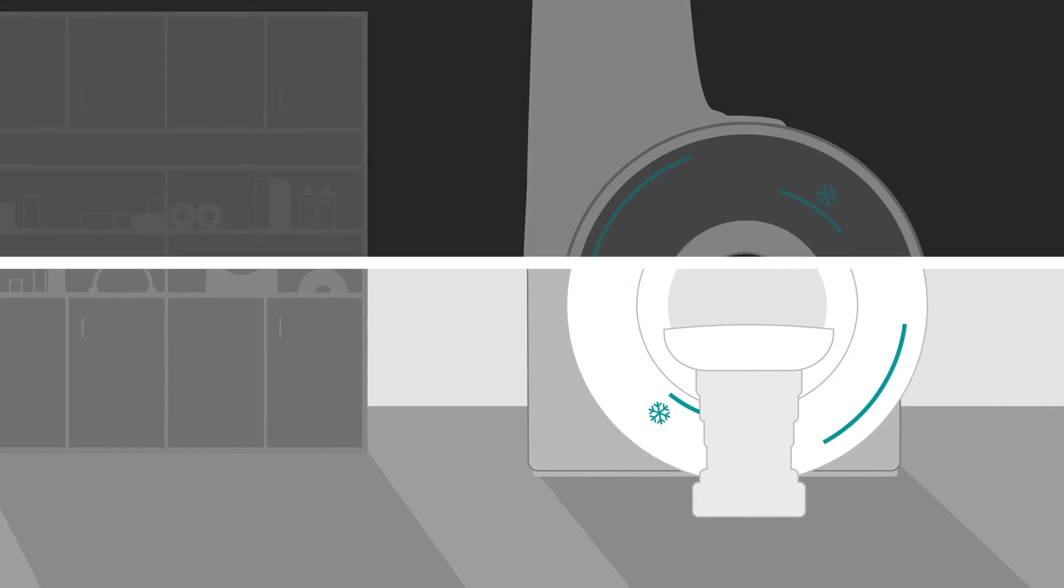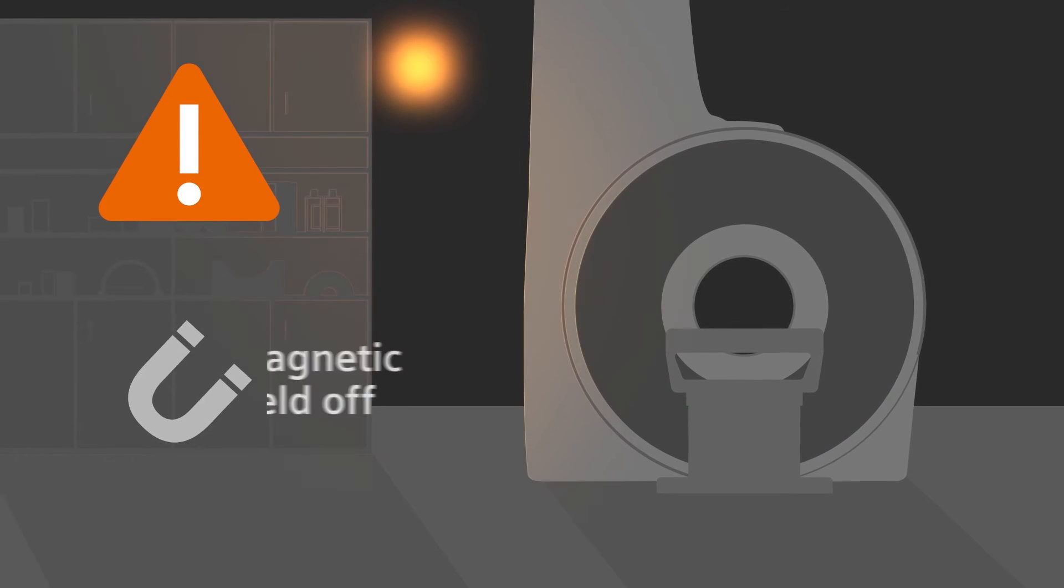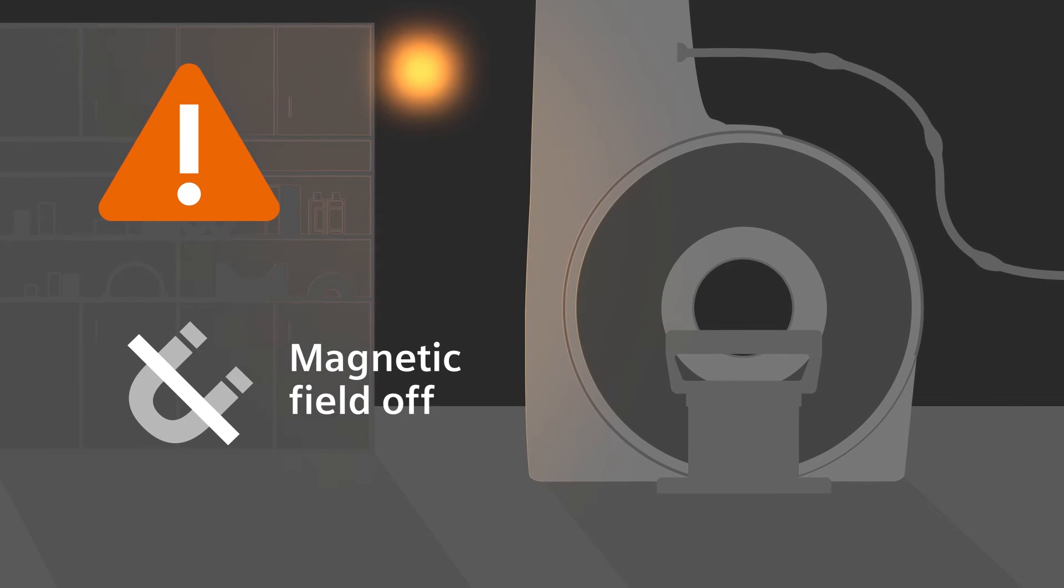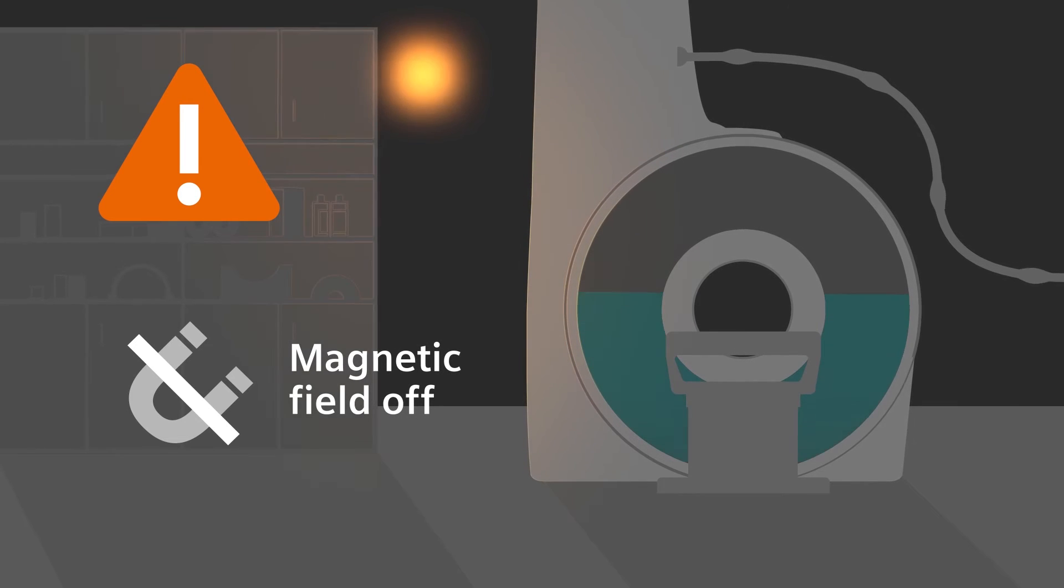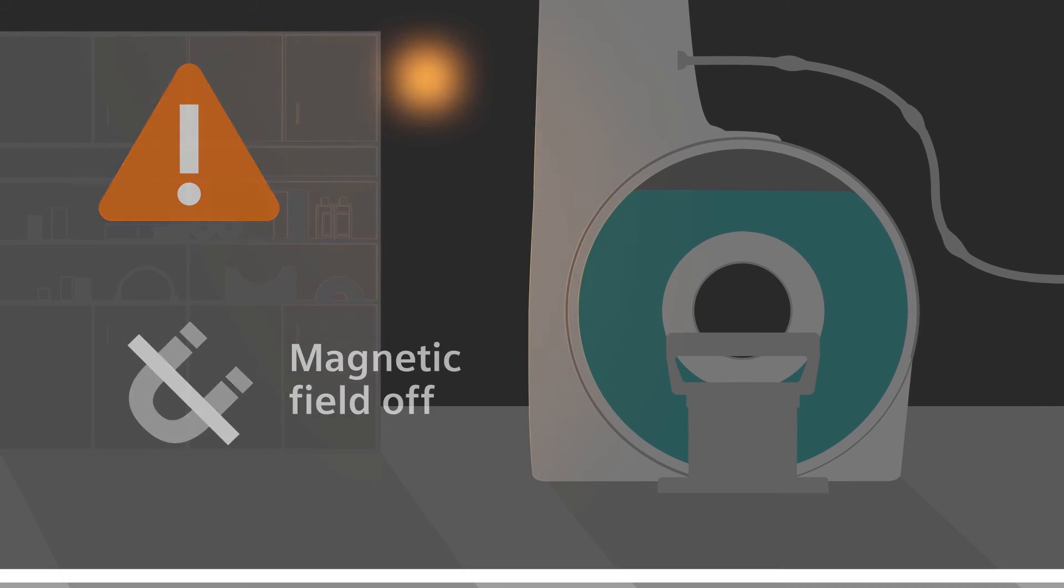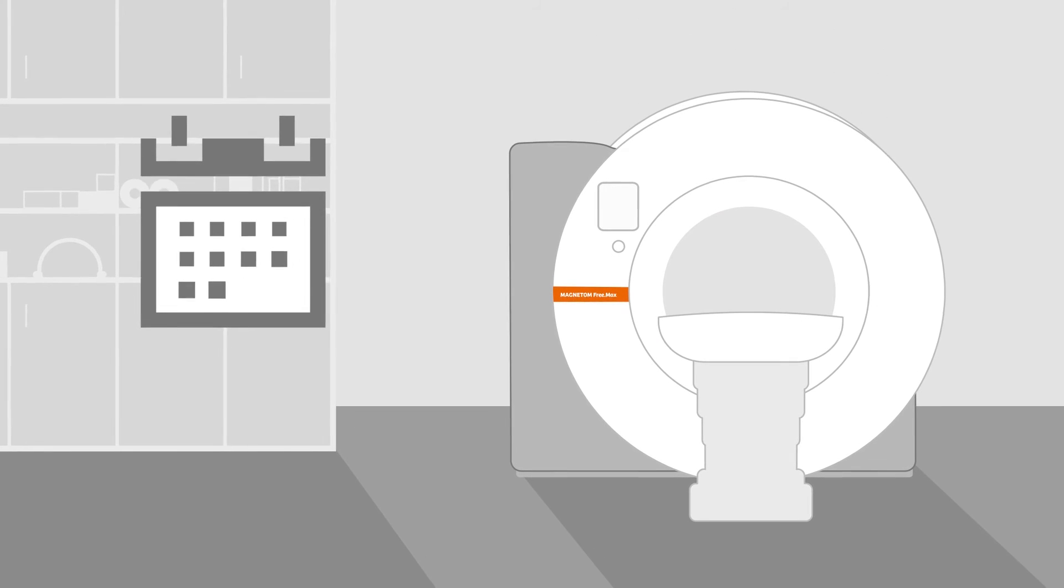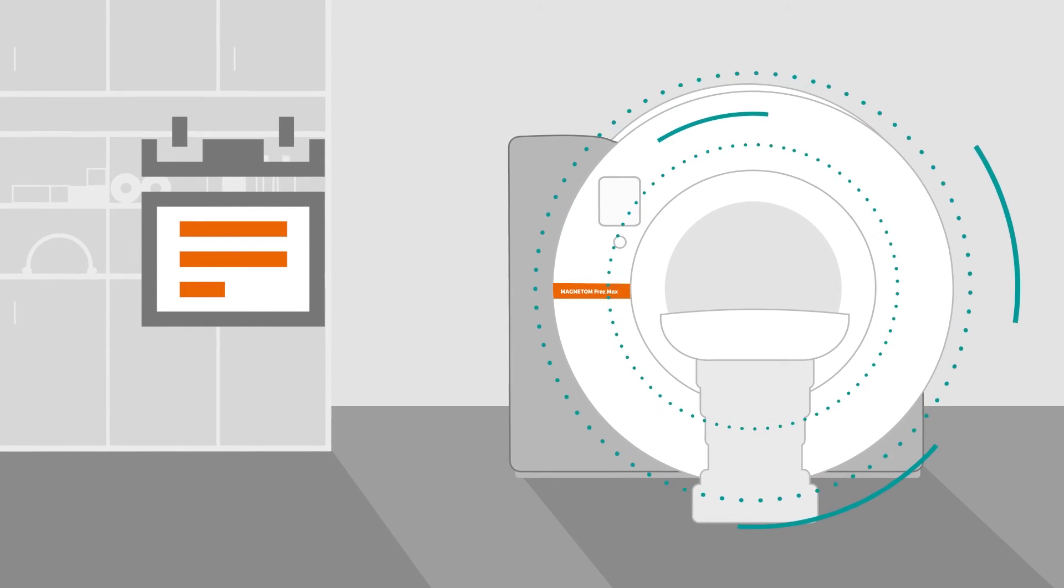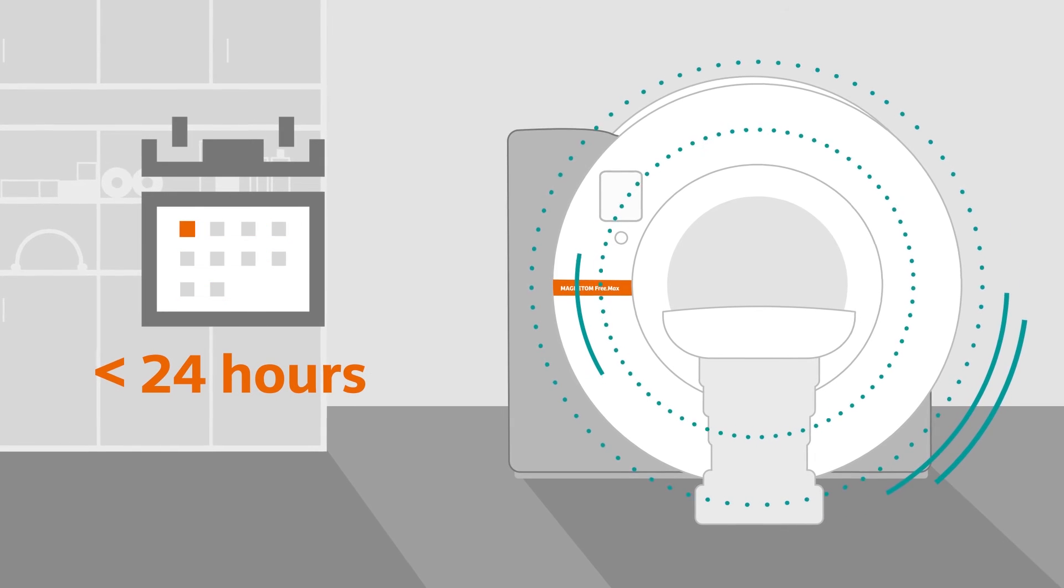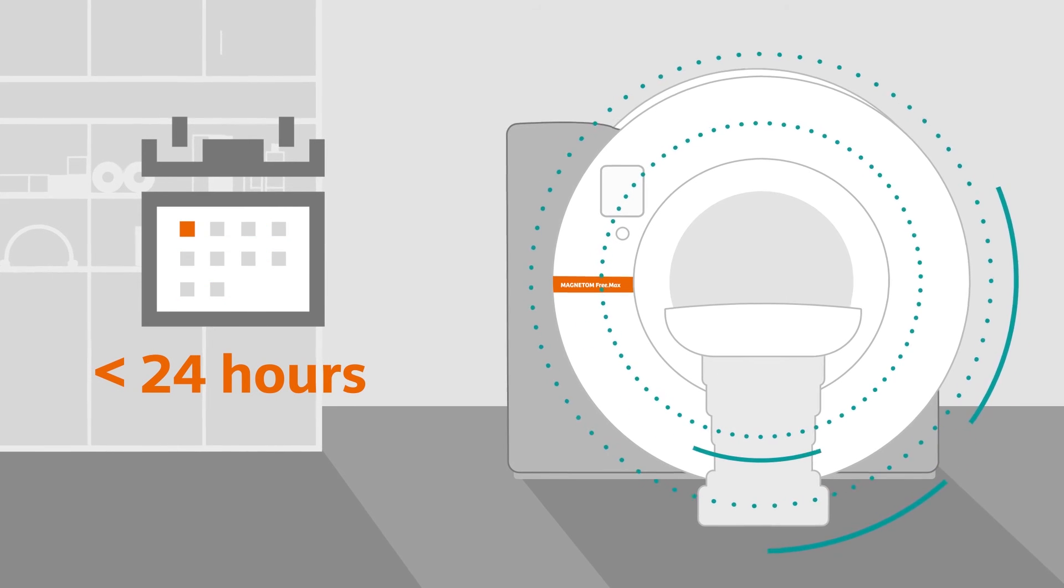For conventional MRI systems, an emergency magnet quench would require a costly helium refill and lead to system downtime of multiple days or weeks. With DryCool technology, Magnetom Freemax is back up and running in less than 24 hours after an emergency magnetic field shutoff.